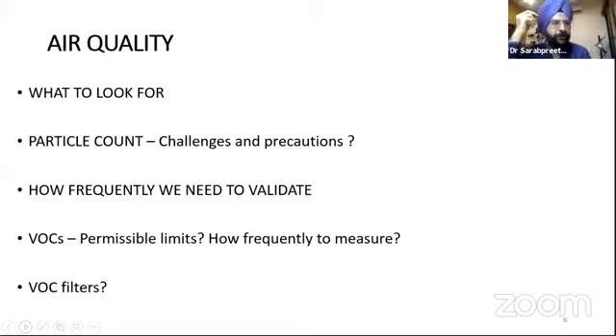It's mandatory every time you change the filter, and the filter change frequency also depends on your location, as Dr. Sujata said. But we should be looking at changing the filter at least once a year, and the particle count should be done at least once a year—if required, twice or thrice a year on a need basis.